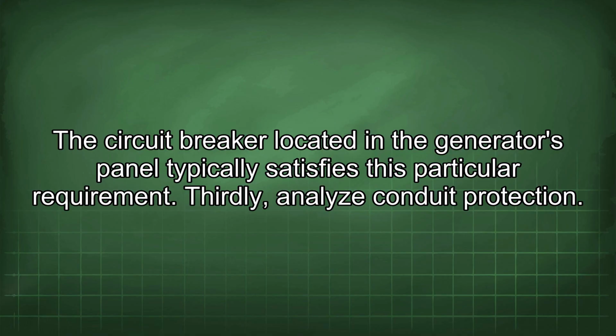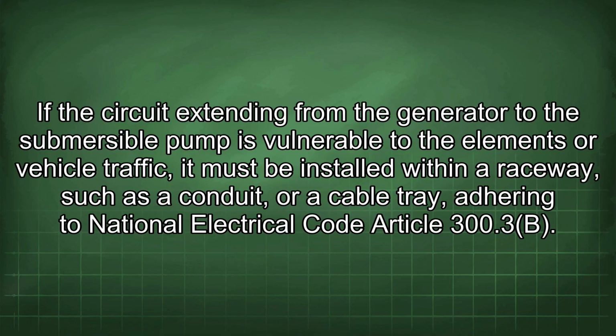Thirdly, analyze conduit protection. If the circuit extending from the generator to the submersible pump is vulnerable to the elements or vehicle traffic, it must be installed within a raceway, such as a conduit or a cable tray, adhering to National Electrical Code Article 300.3b.